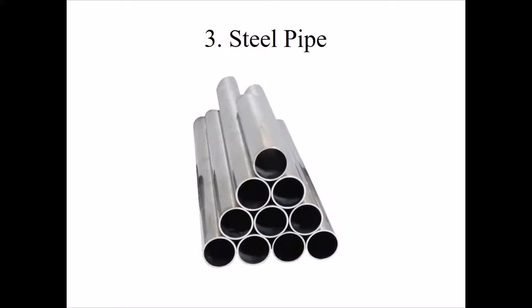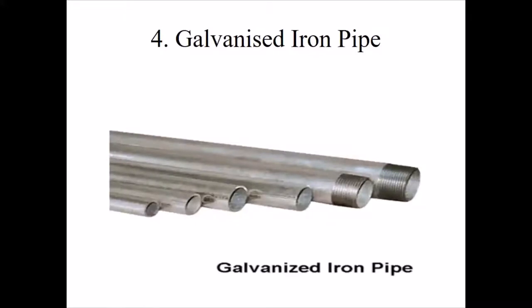Galvanized iron pipes are manufactured by galvanizing iron pipes. They are economical, light, and easy to handle and transport. They can be easily cut, threaded, and joined by sockets. However, these pipes are liable to be affected by acidic or alkaline water and are suitable for service connections.